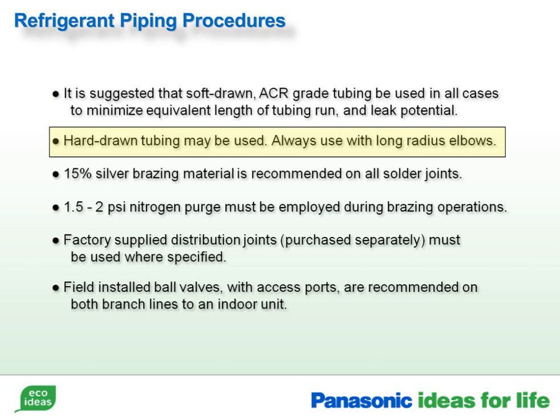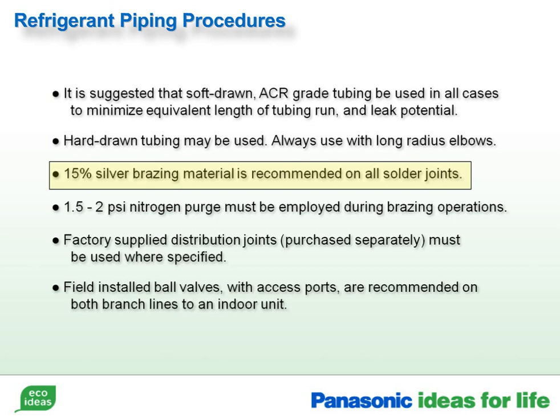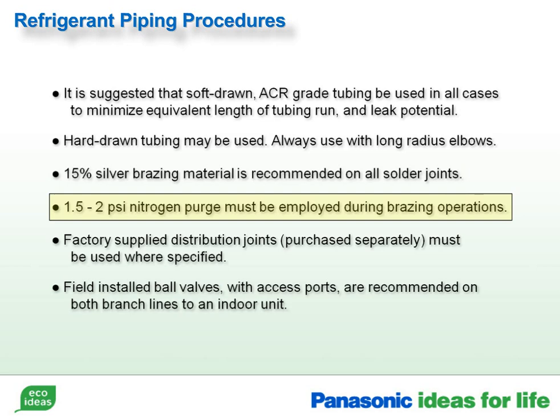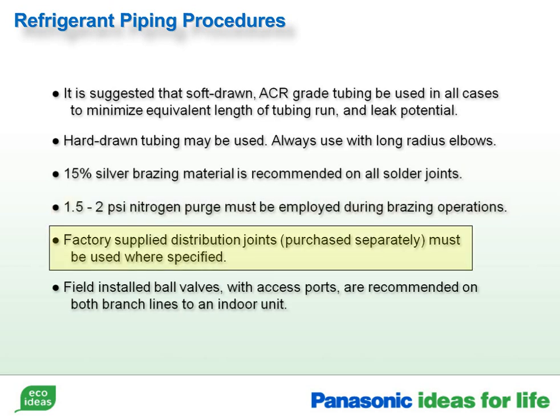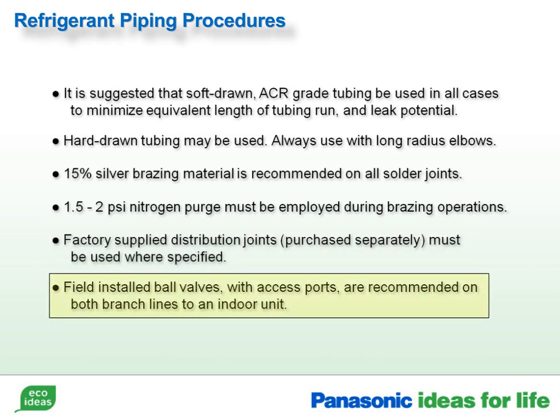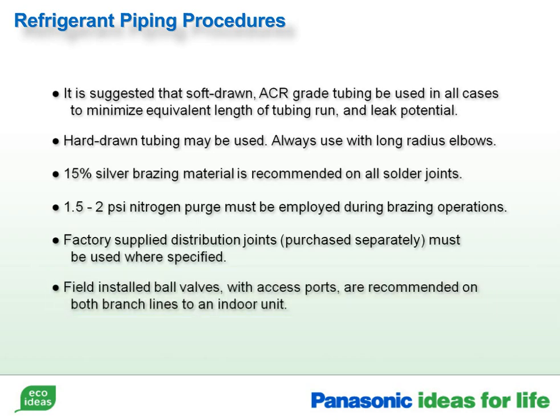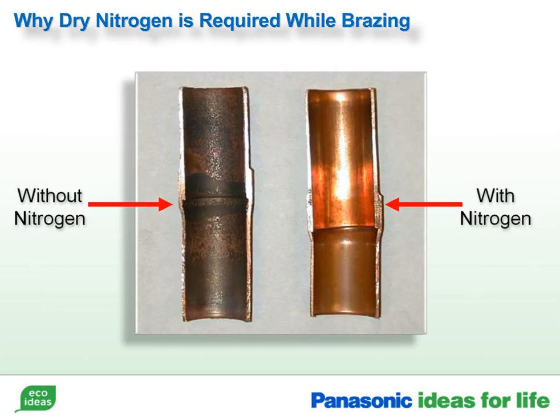Hard-drawn tubing may be used. If necessary, use long-radius elbows. 15% silver brazing material is recommended on all solder joints. A 1.5 to 2 psi nitrogen purge must be employed during brazing operations. Factory-supplied distribution joints, which are purchased separately, must be used where specified. Field-installed ball valves, with access ports, are recommended on both refrigerant lines entering an indoor unit. If a nitrogen purge is not used while brazing, oxidation will occur and contaminate the system.